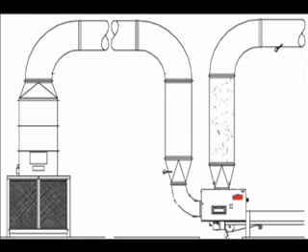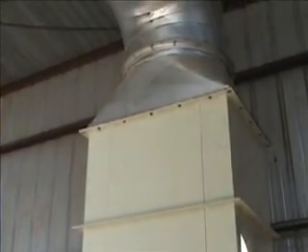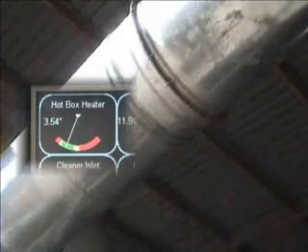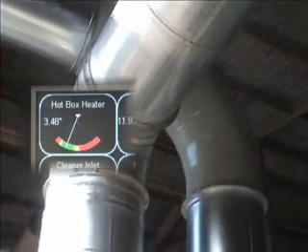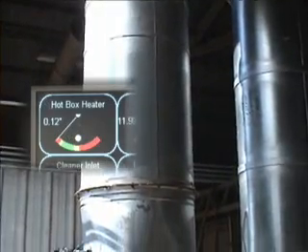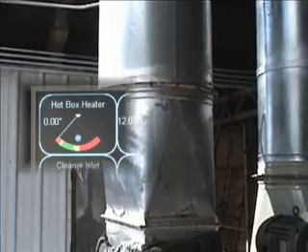Now that we know what we are looking for, let's take a look at some example placement strategies. The example gin we will examine uses a hot box to pick up cotton at the module feeder and take the cotton directly to the drying and pre-cleaning system. Measuring suction at the hot box heater pipe can give us an indicator of how much air is leaking into the hot box. If static pressure falls in this pipe, excessive hot box leakage may be the cause.